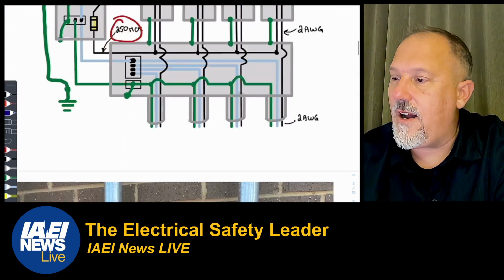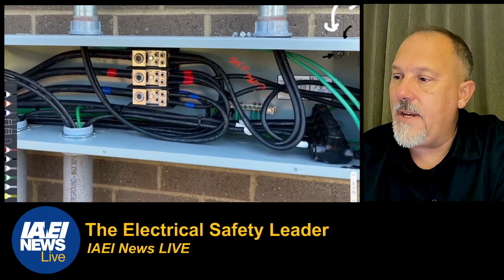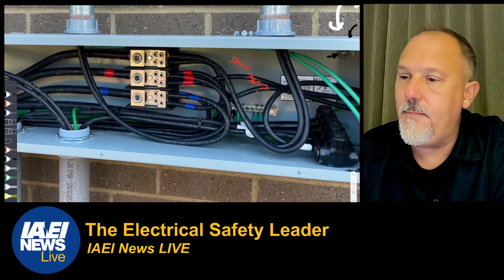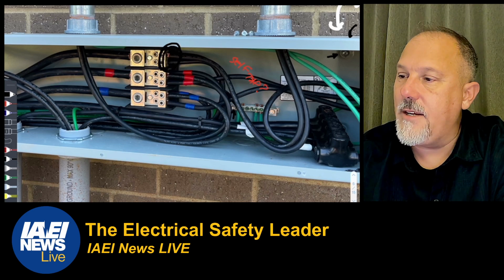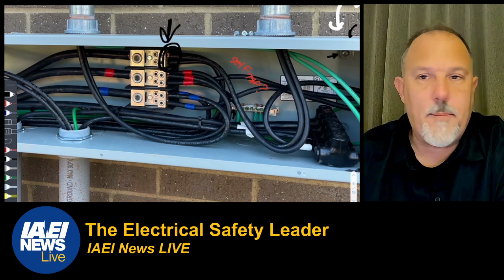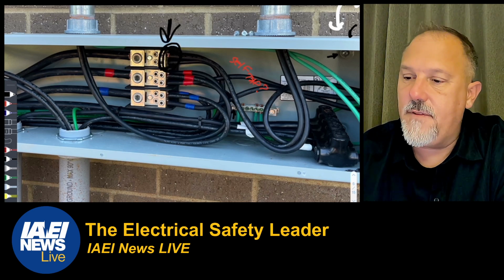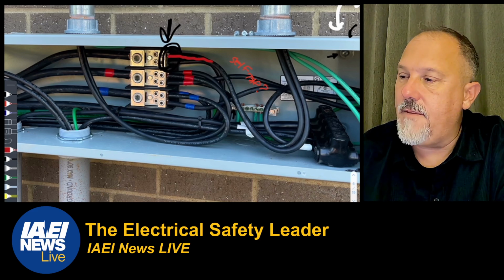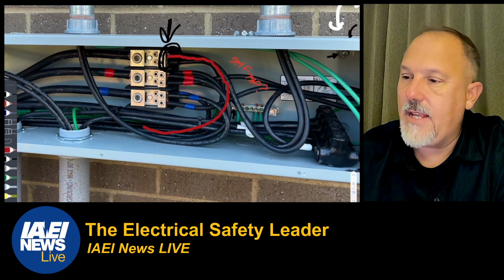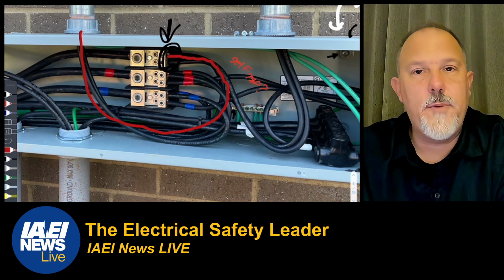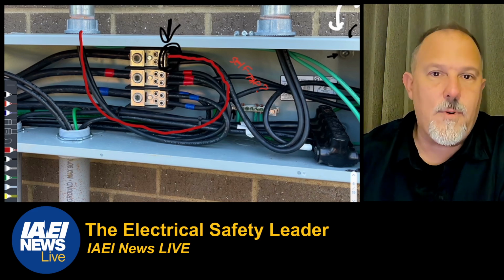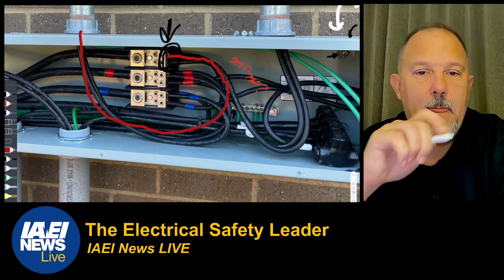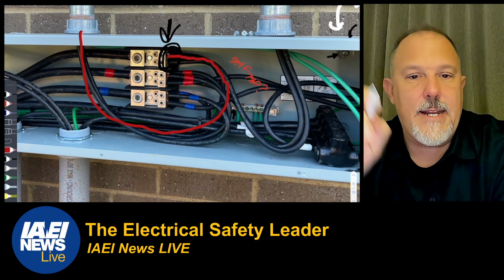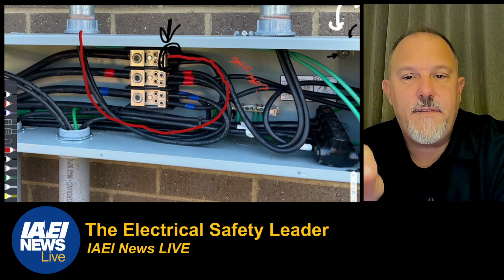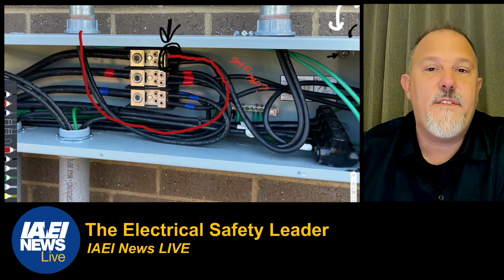And if we look at the trough, where does my tap start? My tap starts right here. That's where the power distribution block is. The length of that conductor that goes down and goes up all the way to the line side, I don't want that to exceed 10 feet. And it can't go outside, except at the point of connection to the feeder, the tap. Okay, and then there's the 25-foot rule.